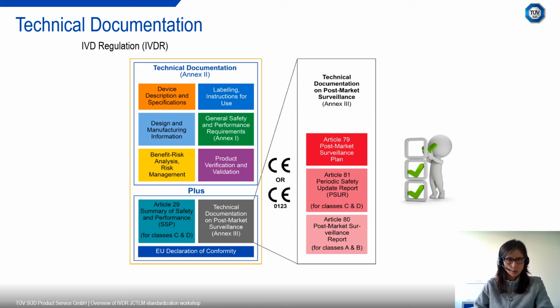The manufacturer should include the post-market surveillance plan, so what they intend to do as part of their post-market surveillance strategy. And after the device has been on the market under the regulation, the periodic safety update report for Class C and D, and the post-market surveillance report for Class A and B. These are documenting the results of the post-market surveillance activities.